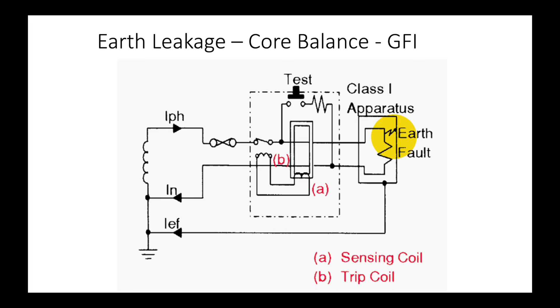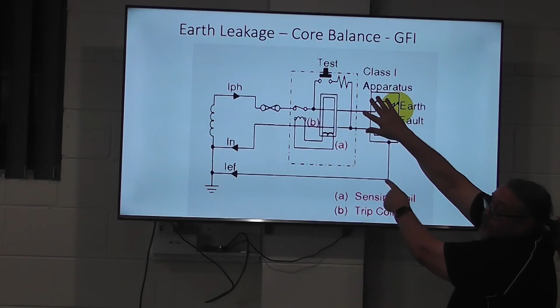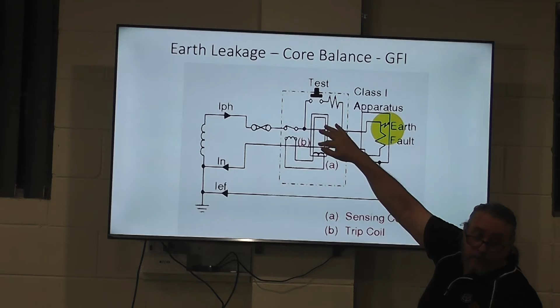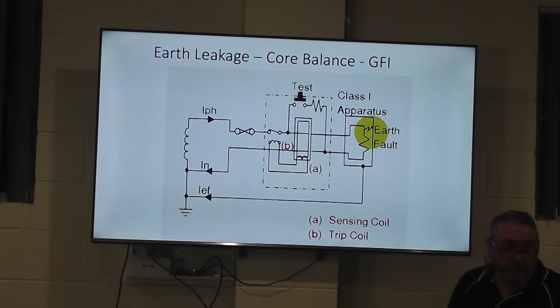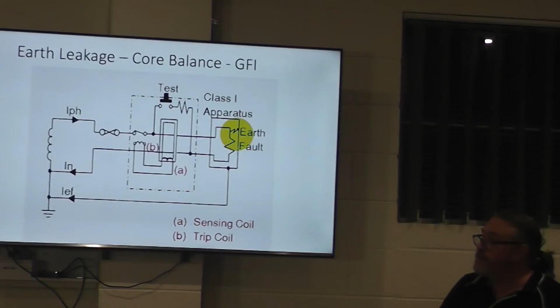So the idea is that if you touch, say, the active conductor like that, there's now a path through my arm to that conductor. And then that means there's a difference in current through this toroid. So that means it'll generate a small current and operate the relay, or trip it. But it relies on a good ground system and your neutral being in the right spot. So without your neutral being connected, if you've got a dodgy neutral, these won't work very well.